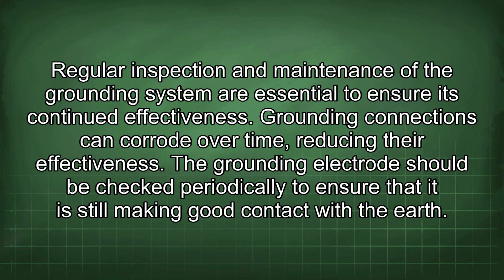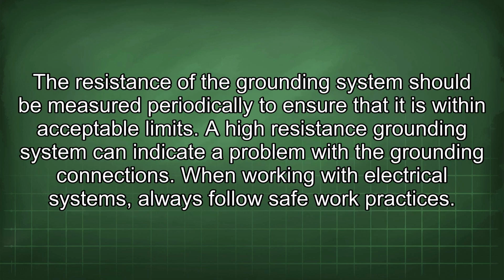Regular inspection and maintenance of the grounding system are essential to ensure its continued effectiveness. Grounding connections can corrode over time, reducing their effectiveness. The grounding electrode should be checked periodically to ensure that it is still making good contact with the earth. The resistance of the grounding system should be measured periodically to ensure that it is within acceptable limits. A high resistance grounding system can indicate a problem with the grounding connections.